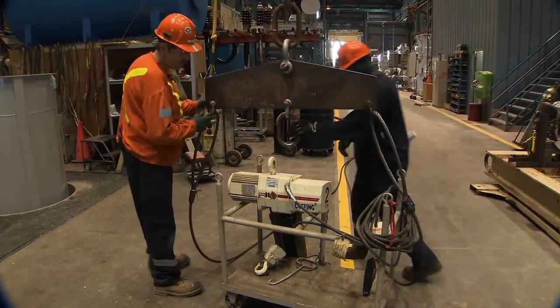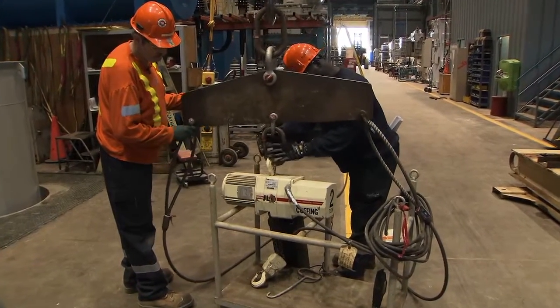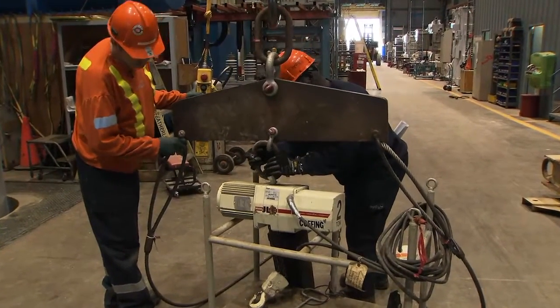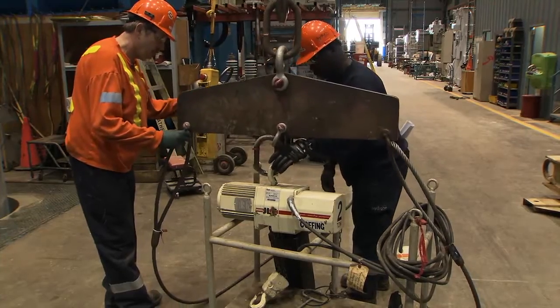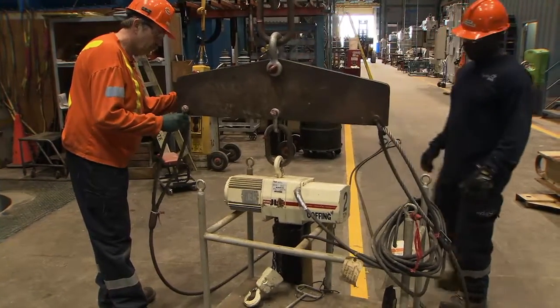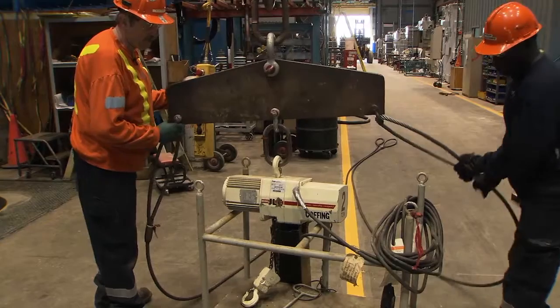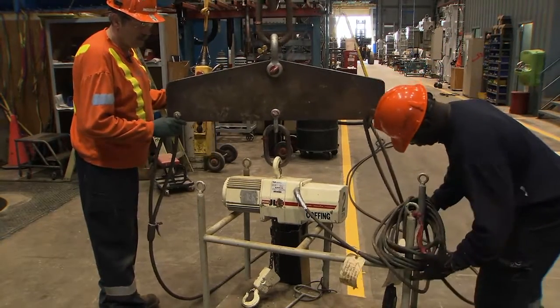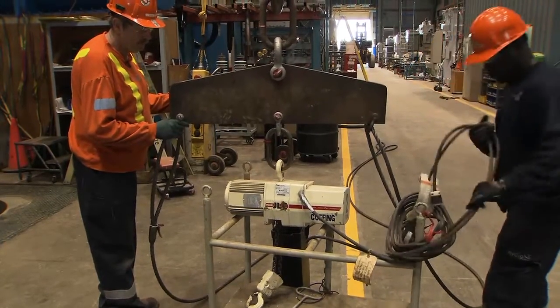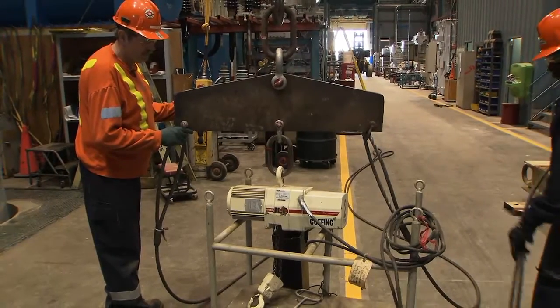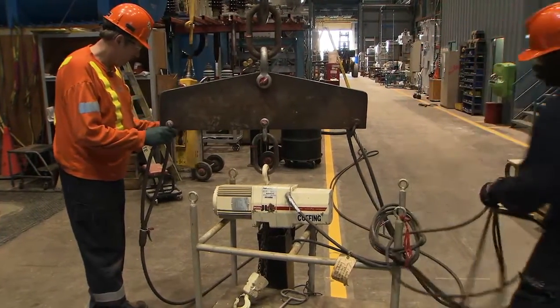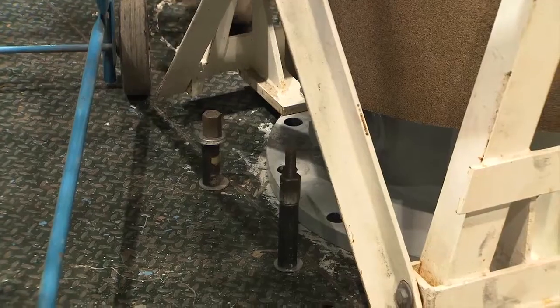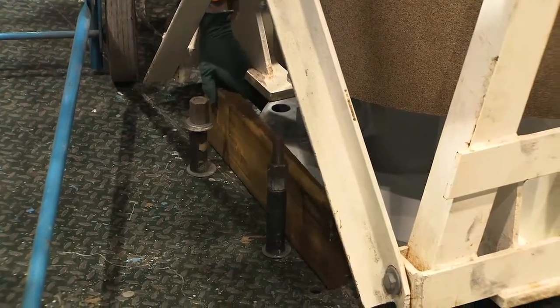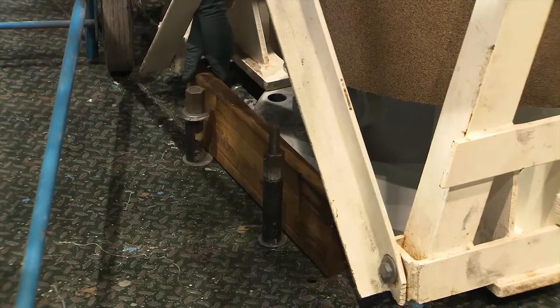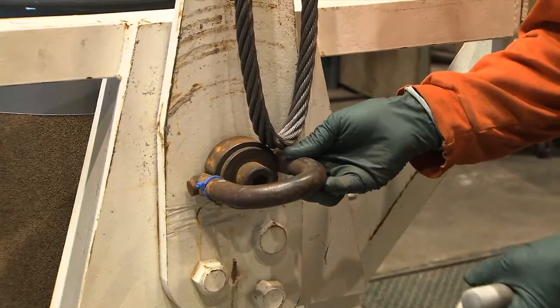Lower the multi-point lifting beam with lifting cables attached at both sides to just above the electric hoist, and then attach the hoist to the crane hook. Unwrap the leads for the electric hoist from around the cart that the hoist is stationed on. Place a block of wood against the vertical metal posts on the side of the service well that the bushing is in. This will prevent the bushing from swaying when it is lifted out of the well.